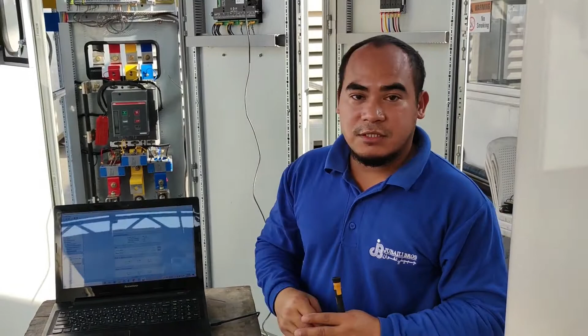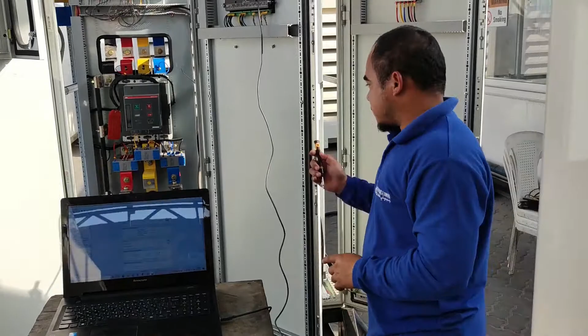The generator is set, and we're going to adjust the voltage and check what the alarm is, what will happen to the other set, generator 1, that has some alarm, so we are going to fix that. In case it also has the problem, we're going to fix that in order to do the voltage biasing, speed biasing, and breaker closing. So let's start and see what problem will occur now.